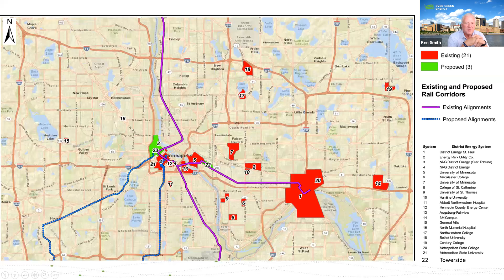Yes, heat pumps do have their limitations on what kind of temperatures they can produce, and we can get into that a little bit later on in the fourth generation. I've got a slide coming up on that. For lower temperatures, particularly for buildings, if you can get the temperature of the systems below 180, even down to 140 or so, you can utilize heat pumps quite effectively. In higher temperature systems, let's say 200 degrees and more, that's challenging. There are some technologies out there, but they tend to have refrigerants like ammonia, and I've seen that in Norway, for example, where they're using ammonia-based heat pumps to integrate into higher temperature systems. So heat pumps play a role, and there's a lot of work going on to advance the technology in heat pumps so they can produce higher temperatures. That's a very good question.